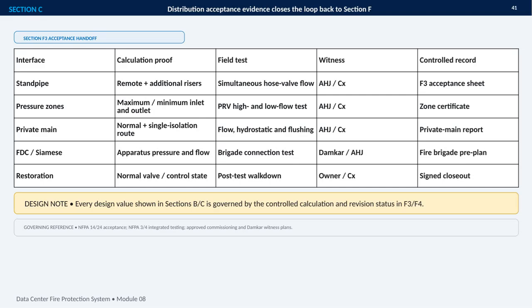This slide shows how acceptance evidence closes the loop from design through field verification and controlled handoff. Every interface must connect calculation proof, a witnessed field test, and a controlled record. For the standpipe system, that means confirming the remote and additional risers, then demonstrating simultaneous hose valve flow, with AHJ or commissioning witnesses and an F3 acceptance sheet.